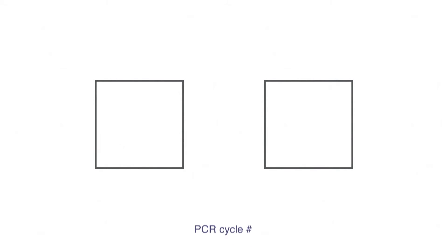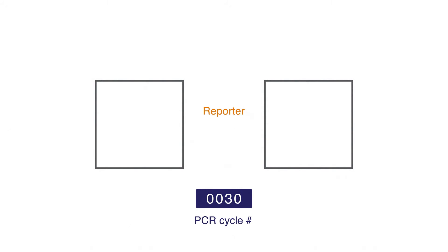Here's how it works. Say that we're looking at two specific wells in my reaction plate. I pipette exactly the same amount of the same sample into each well and amplify in real-time. A short time later, we reach cycle 30. As for every cycle, the instrument will take a reading of my reporter dye. I expect the two readings to be identical, since I started with the same reaction components. Unfortunately, they're not, due to a system inconsistency between these two wells.